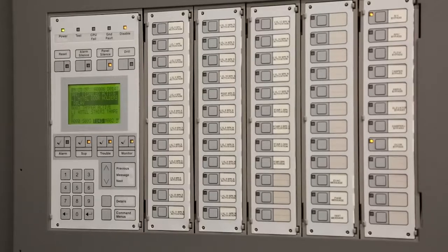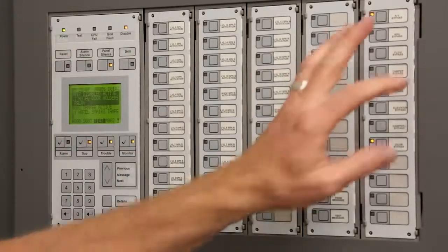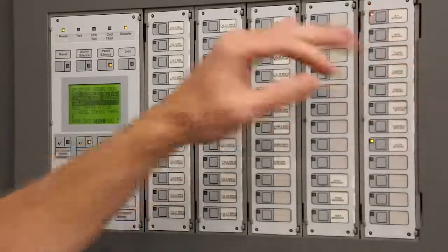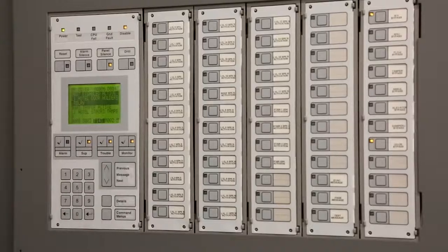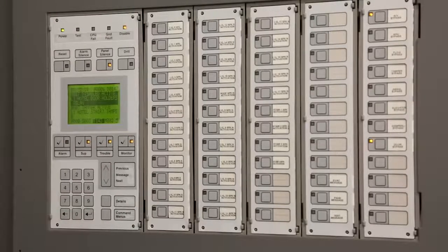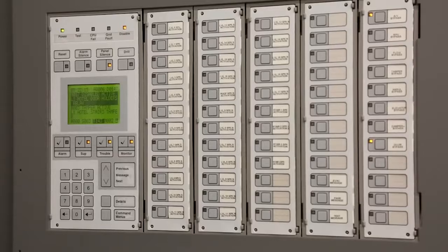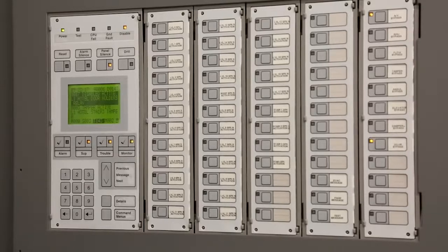I will say one thing though: if you are in alarm, do not bypass when you're in alarm. There will be a problem, okay? Only bypass when the panel is out of alarm. For instance, if you bypass the AVs in alarm and you go to reset, they're going to be re-triggering again, because you're trying to tell it to stay out and then you're doing it again.